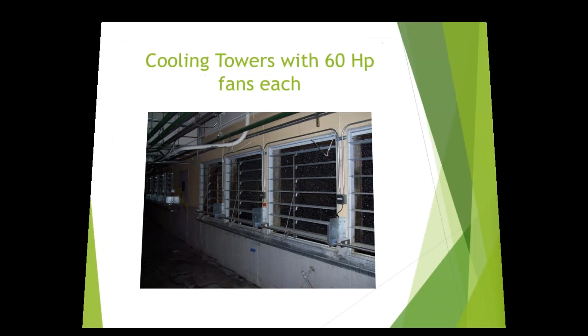So to go back, let's do this, don't mean to get everyone dizzy. Right on this hatch, I had one of these things here. My fan line is right there, meaning I'm drawing in air 2 floors below through my inbound and outbound ramps, and the gate is open, so I'm constantly sucking in air because I run chilled water 24/7, so the cooling tower fans are always drawing air into the garage. That's very important, it's an inherent quote-unquote problem or situation for Transamerica.